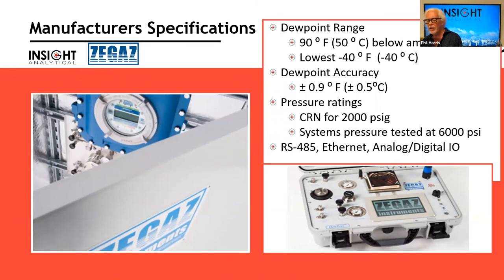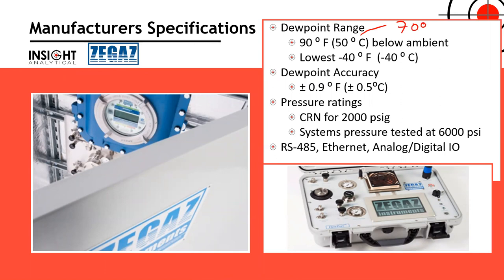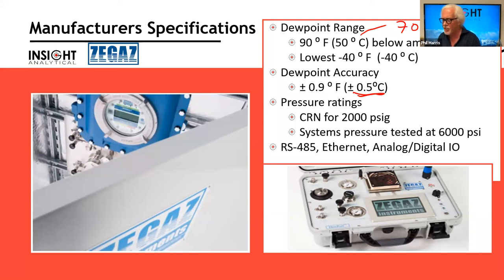Specification wise, we can cool, I think I still have this right. Sort of, you may correct me here. I might actually be higher than that, more than 50 degrees C below ambient. Yeah, we've actually increased that to close to 70 degrees, depending on a couple of factors, but it is closer to 70 degrees now. So if the analyzer is running at 30 degrees C, you can cool down to minus 40, a 70 degrees C differential. Dew point accuracy is typically in that half a degree C range.